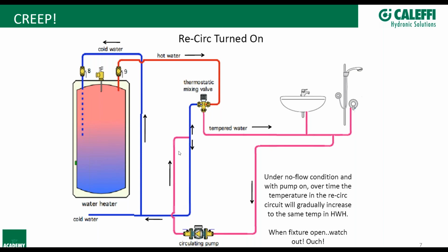Obviously, you've got your recirc coming back, and the mixing valve is sending out 120 degrees. Your recirc's coming back maybe at 110 or 115. So you've got 110 or 115 coming into the cold inlet, and then you actually have it reverse flowing here, going back through the tank, and then all the way around back to the hot inlet. And the biggest issue is that most thermostatic mixing valves do not have the ability to completely close off the hot or the cold inlet.